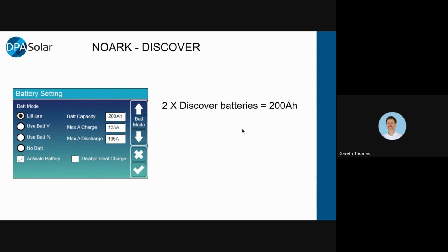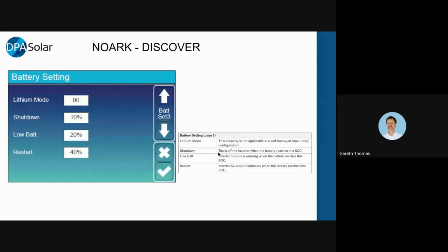I've got a quick little example here of a Noark system paired with a Discover battery. This is with 2 Discover batteries, so they're 200 amp hours. Set it to lithium because it's a managed setup. Max charge rate is 135 amps. It's an excerpt from the manual. We've set our shutdown at 10%, low battery warning at 40%, our restart at, low battery at 20 and our restart at 40.